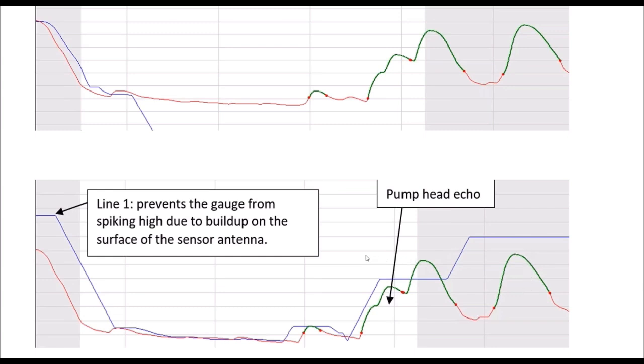Now, when you're setting up one of these lift stations, the first thing you're going to want to do, you have to expose all of the unwanted obstruction. So therefore, you got to pump this down to your low suction point to expose the pump head. You got to get this pump head into view so you can go in and map it out. You cannot map it out ahead of time because you don't know what the signature looks like until you pump it to the low suction point. So when you pump this guy down to the low suction point, you put that manual edit in there, and now the sensor will now work reliably for years to come.